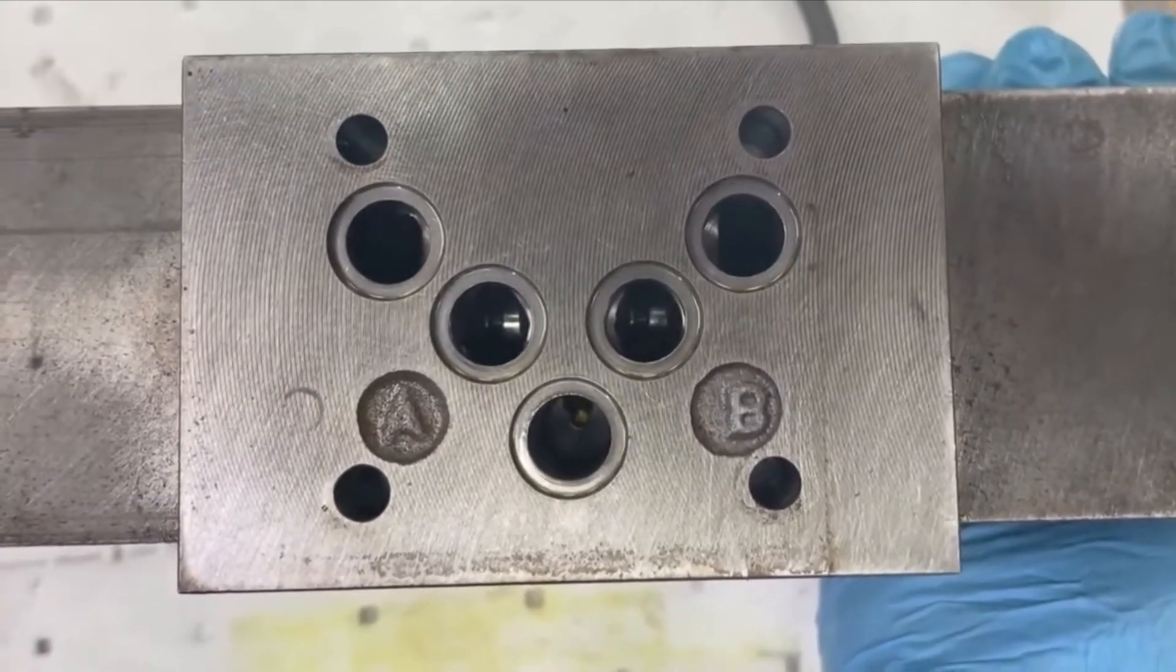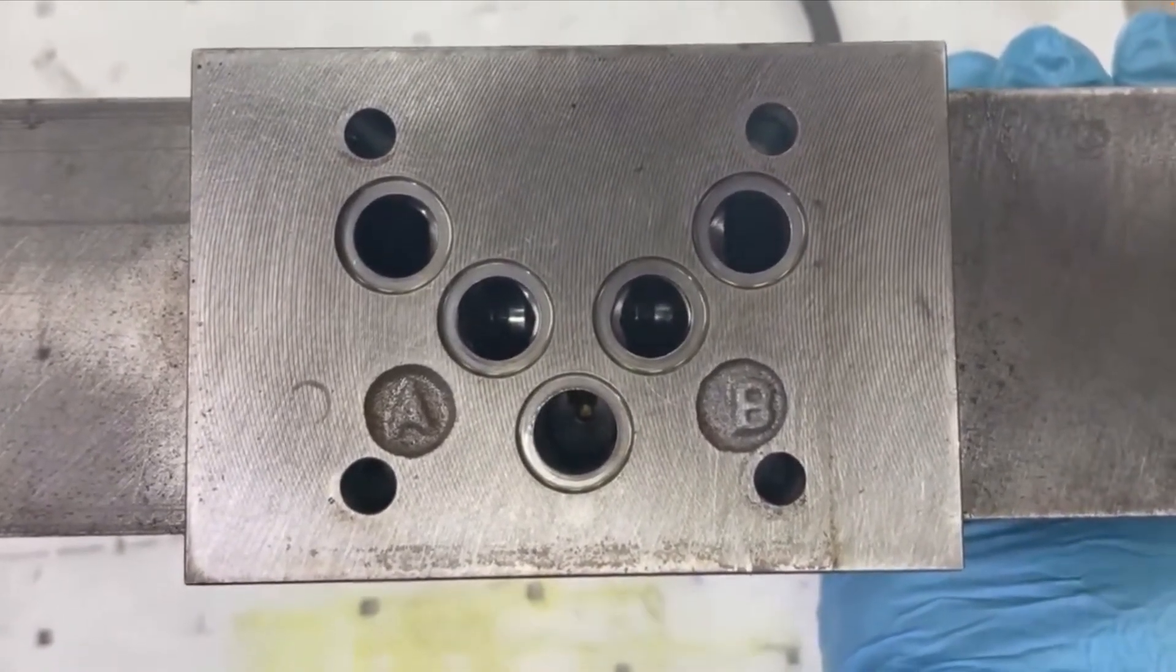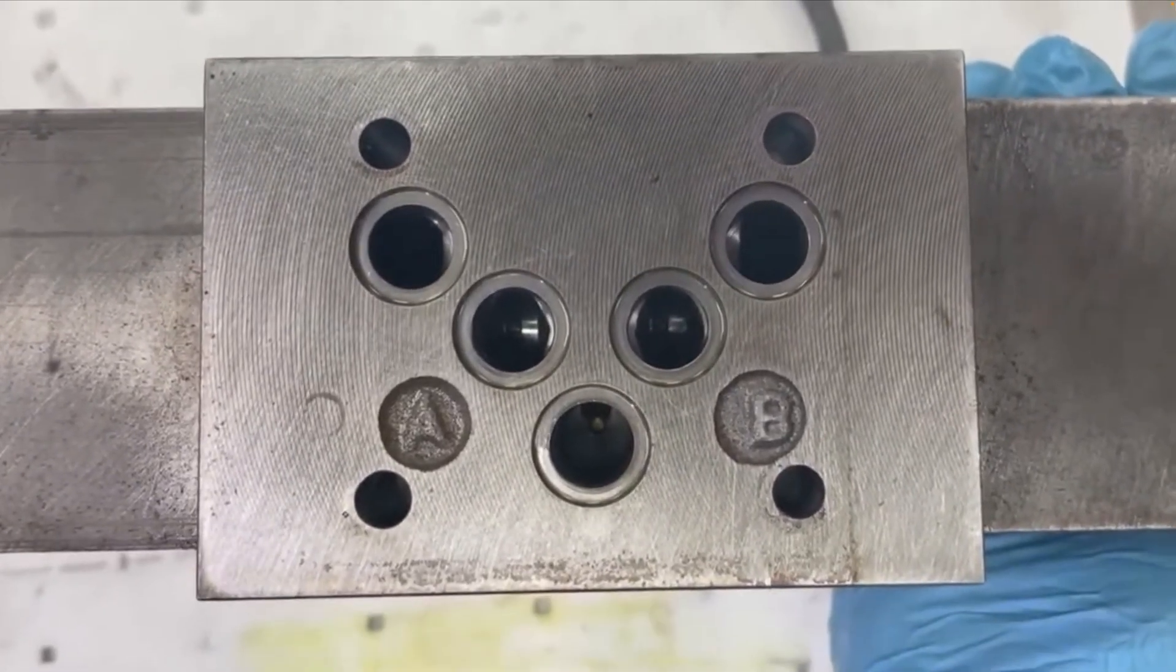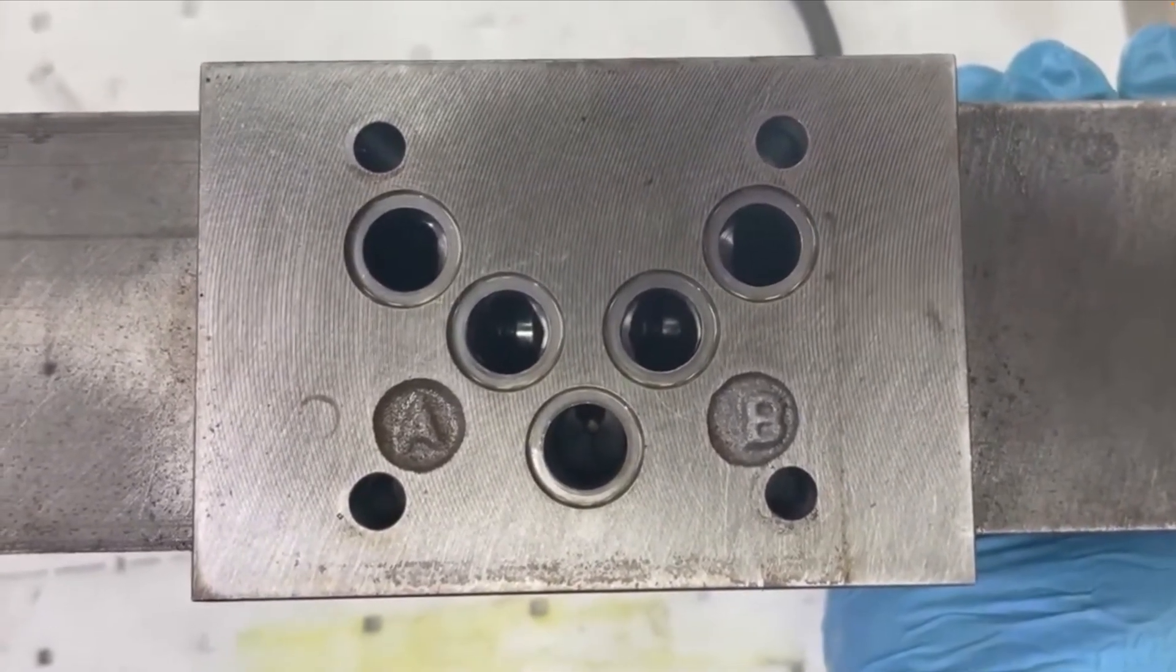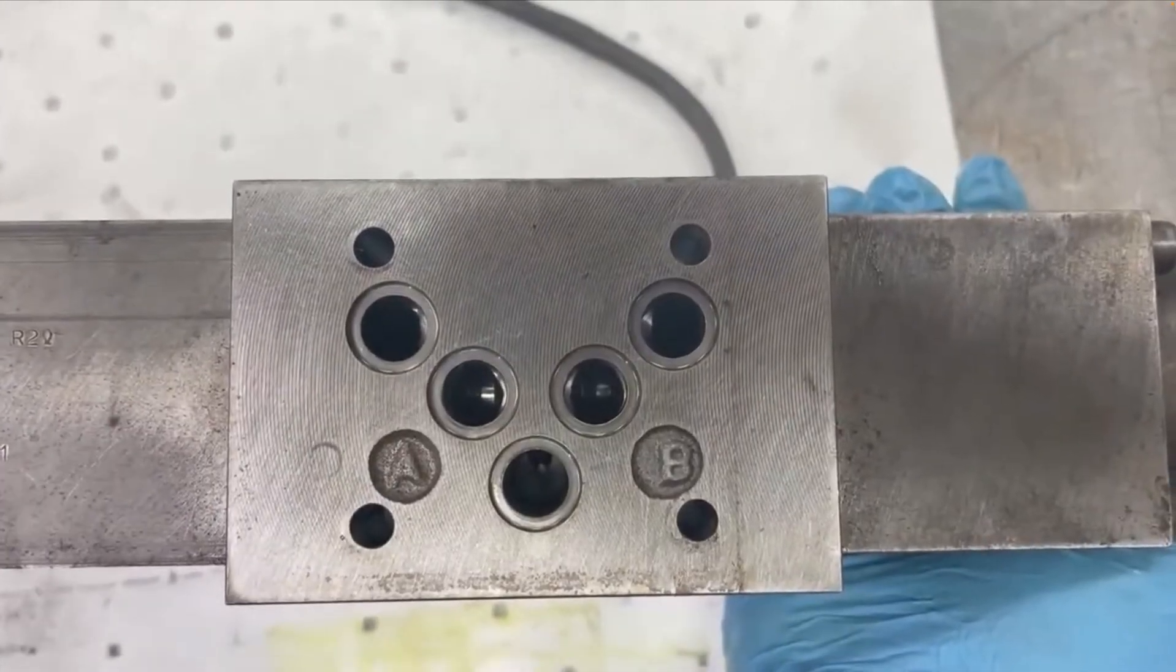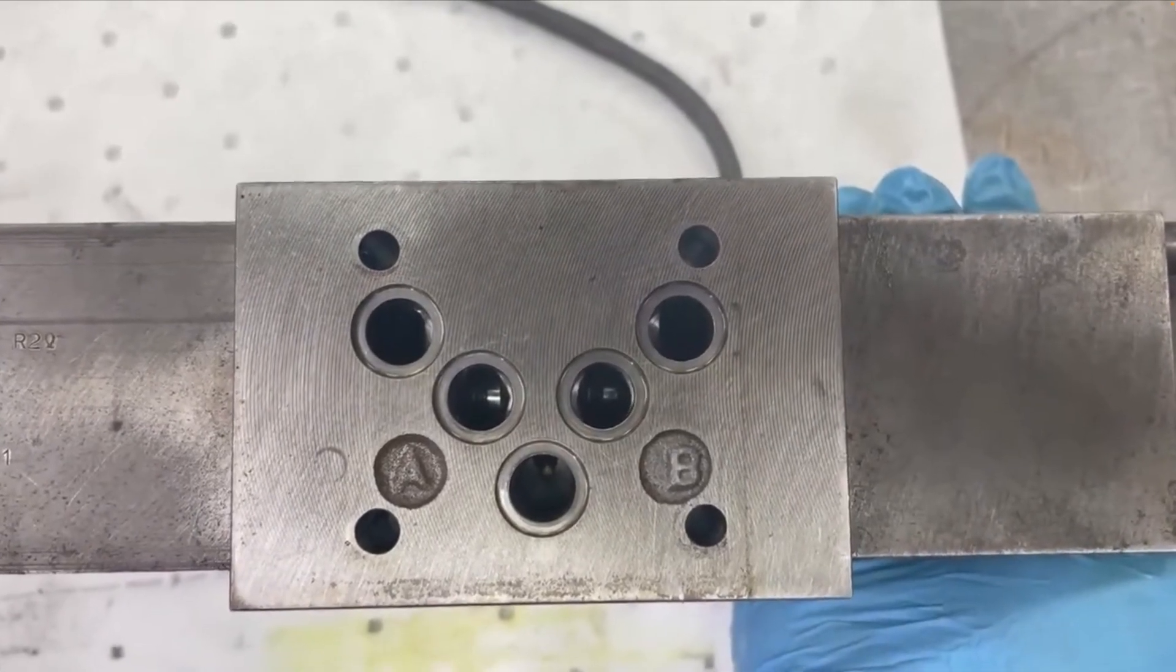So this tells us when we supply a command signal that the outboard electronics of this valve is doing its job. It is shuttling the spool to the left and to the right according to its response curve.